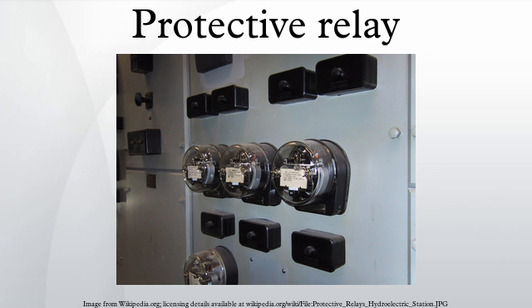Armature-type relays have a pivoted lever supported on a hinge or knife-edge pivot, which carries a moving contact. These relays may work on either alternating or direct current, but for alternating current, a shading coil on the pole is used to maintain contact force throughout the alternating current cycle. Because the air gap between the fixed coil and the moving armature becomes much smaller when the relay has operated, the current required to maintain the relay closed is much smaller than the current to first operate it. The returning ratio, or differential, is the measure of how much the current must be reduced to reset the relay.